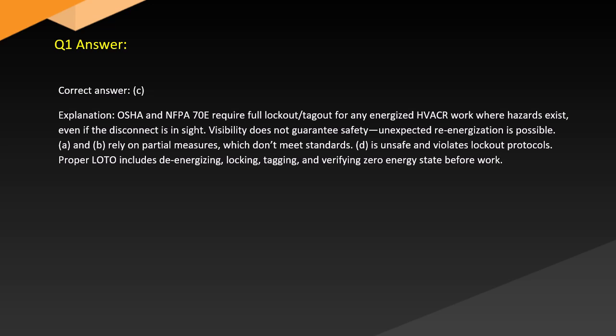Answer. Correct answer: C. Explanation. OSHA and NFPA 70E require full lockout-tagout for any energized HVAC work where hazards exist, even if the disconnect is in sight. Visibility does not guarantee safety. Unexpected re-energization is possible. A and B rely on partial measures which don't meet standards. D is unsafe and violates lockout protocols. Proper LOTO includes de-energizing, locking, tagging, and verifying zero energy state before work.